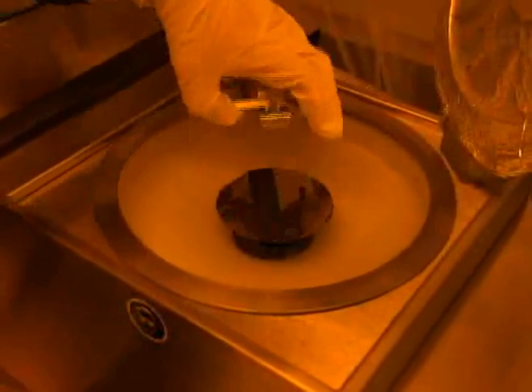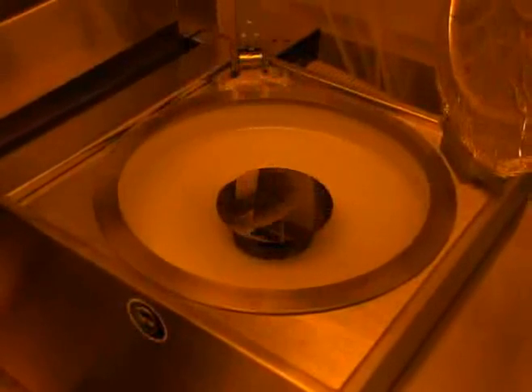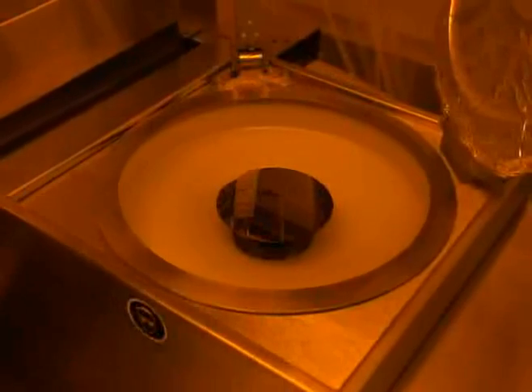Now, carefully raise the two rods and then the centering tool. Be careful when handling the centering tool — quickly dropping or bumping the tool can cause your wafer to break. At this point, you should line the bowl of the spinner with Texwipes to absorb the splashed photoresist.